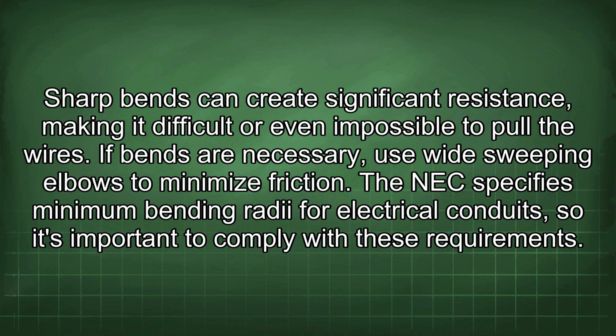Sharp bends can create significant resistance, making it difficult or even impossible to pull the wires. If bends are necessary, use wide sweeping elbows to minimize friction. The NEC specifies minimum bending radii for electrical conduits, so it's important to comply with these requirements.